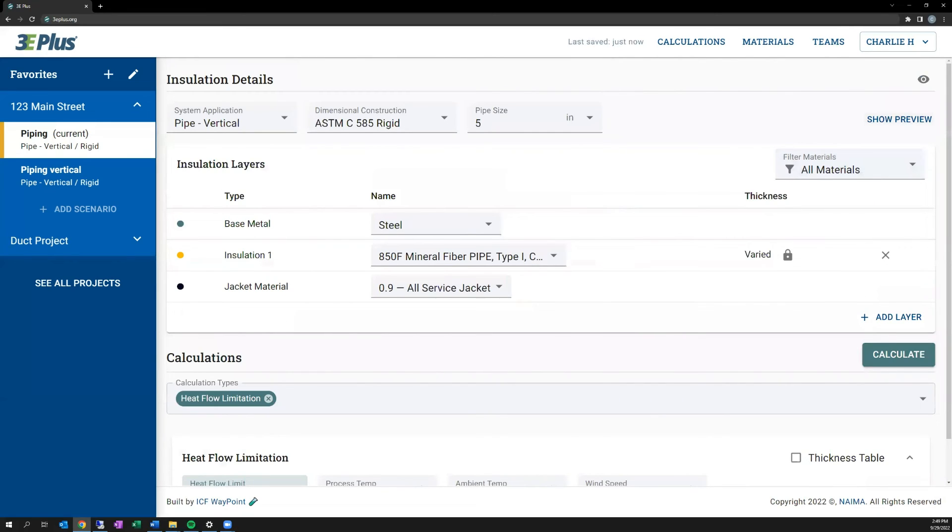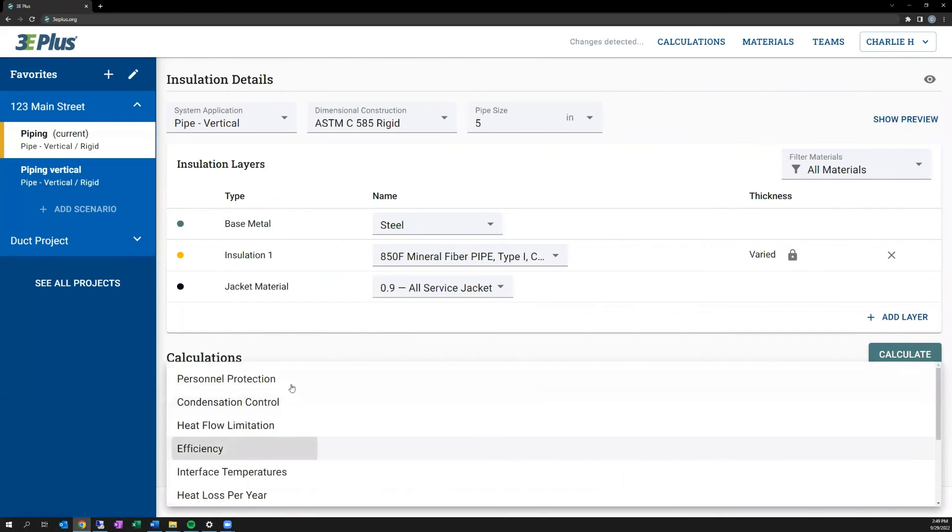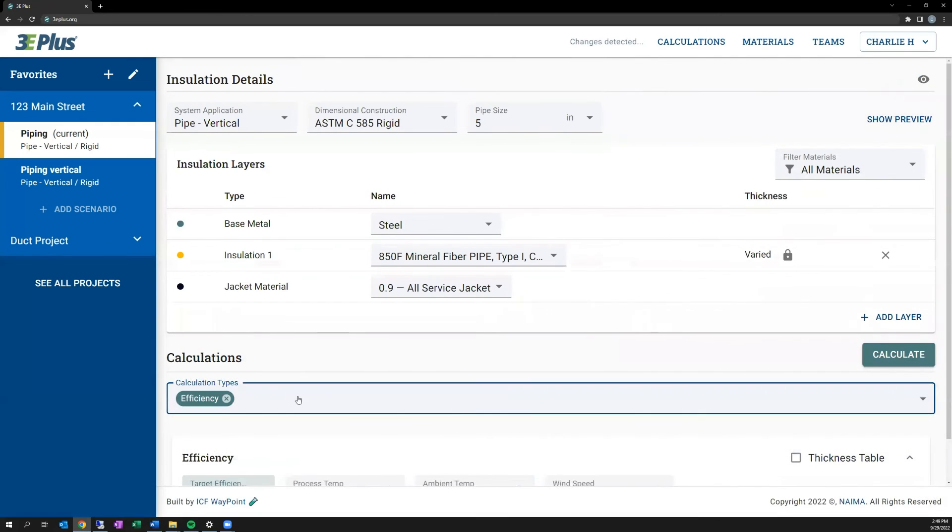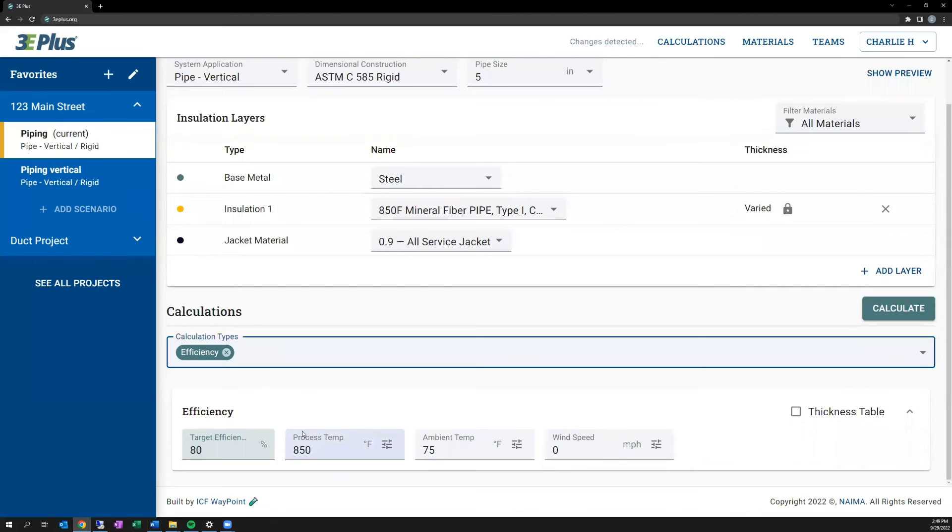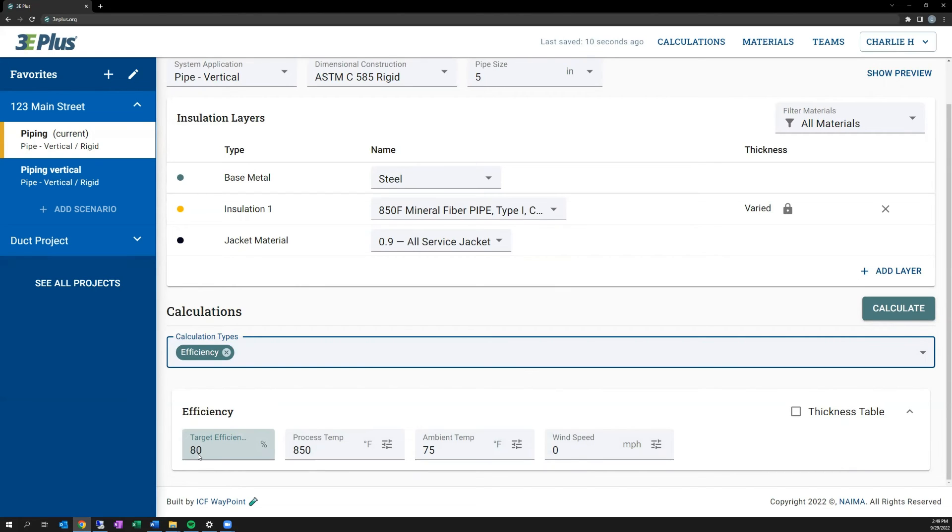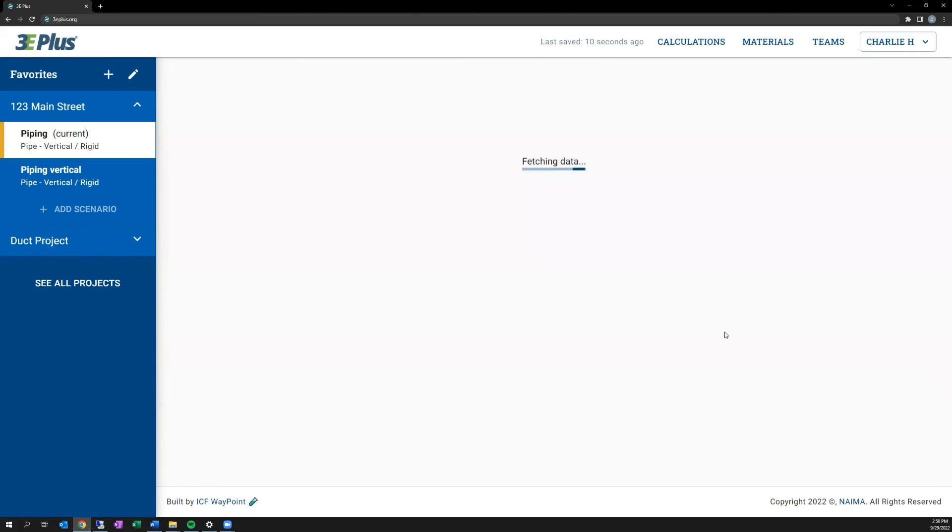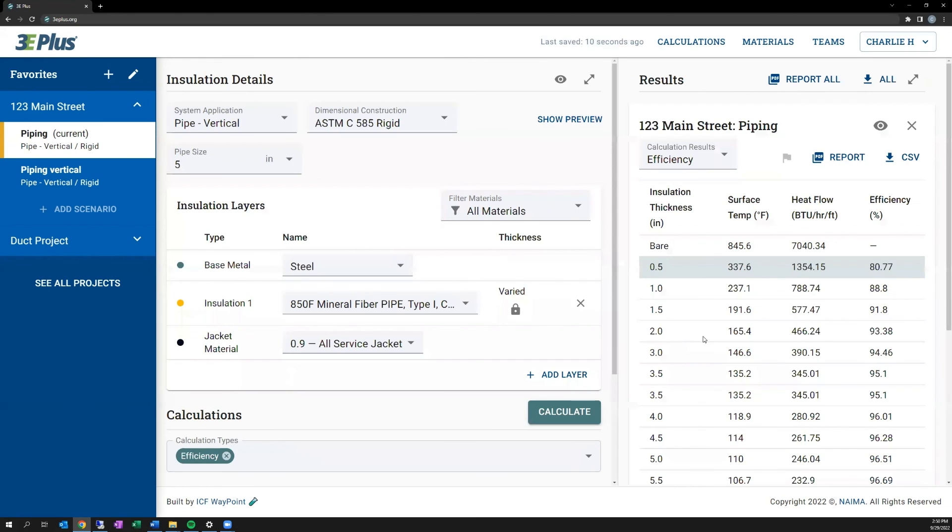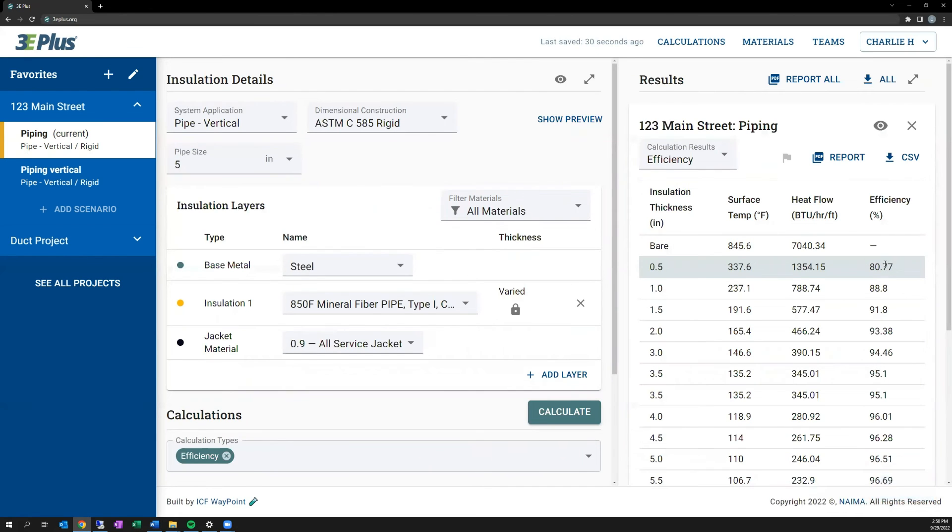So the final target calculation we have is the efficiency calculation. Similar to the other target calculations, it had the foundational inputs for heat loss, the process temp, ambient temp, and wind speed. But it now includes the target efficiency value. This is the target that reduces the heat flow through the pipe when compared to uninsulated piping. So in this case, I want to say it's 80% efficient. So it's going to block or reduce the amount of heat loss in the pipe by 80% compared to an uninsulated pipe. And when I click calculate, it'll highlight the lowest amount of insulation that's required to meet that efficiency target.